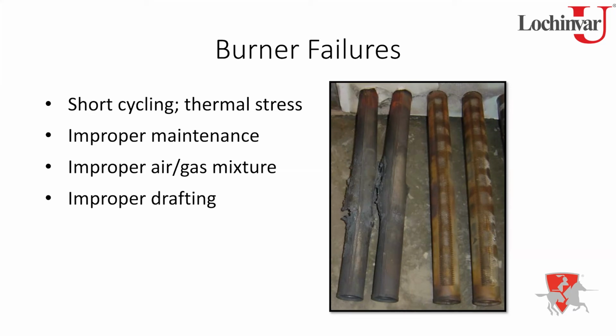Other issues that will cause overheating, again, just a bad gas air mixture, right? You're overfiring it, too much gas, not enough air. So either from air pressure or a lack of oxygen, or you've got a bad vent system, not enough draft. Yeah, and another thing that I always do, and this goes not just for negative draft appliances, this goes for positive category 4 appliances.